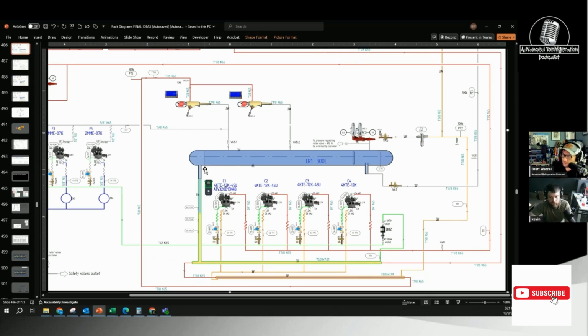So the oil will sit on the bottom and end up going into this little standpipe. There's a diverter piece to help prevent the oil from going out there. That's also why the liquid feed off the right-hand side here is raised up a little bit, so oil cannot just go directly down and out through the liquid line to the cases. The oil will sit in the bottom of the standpipe, go through here, and then get redistributed to the compressors. The problem is, what flash tank pressure are you running? What's saturated? 515. Okay, I was confused. So what, 36 degrees, something like that? Yeah, something like that.